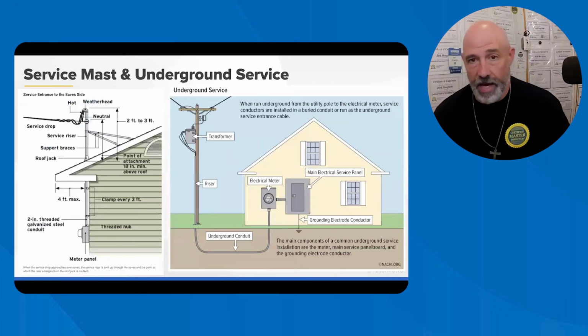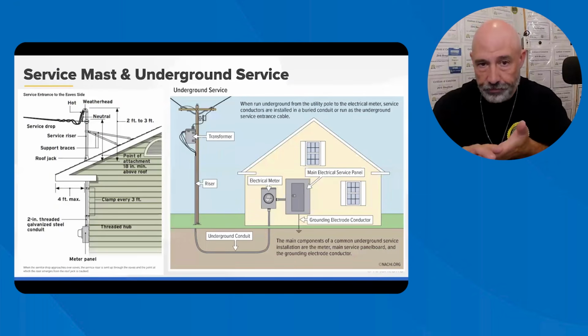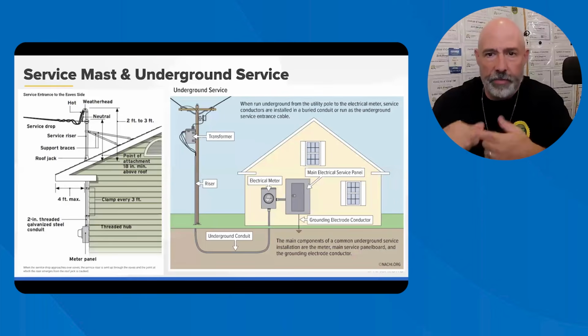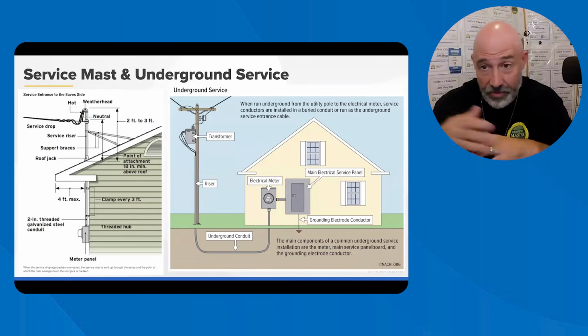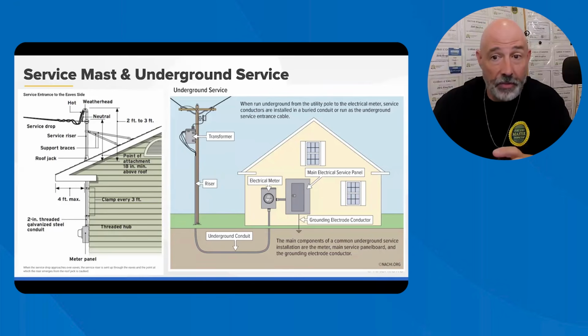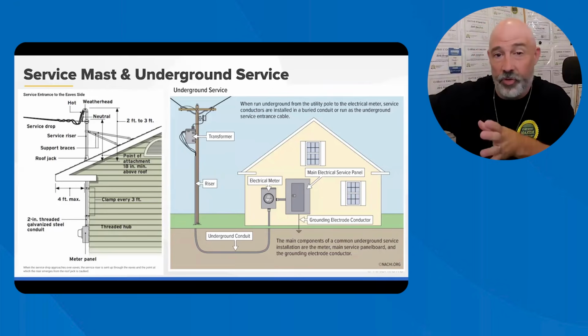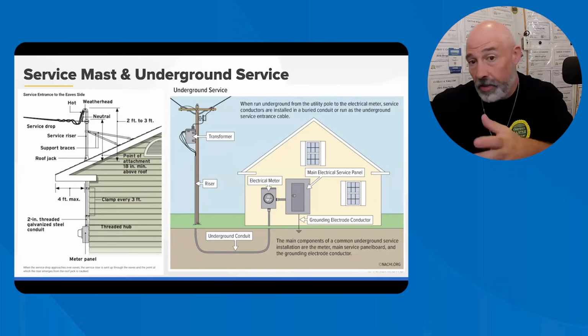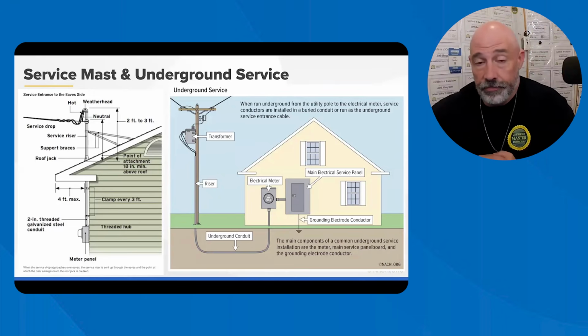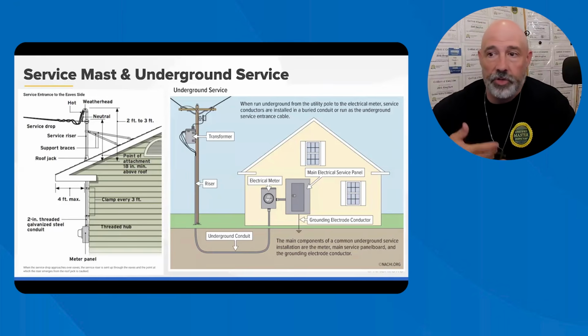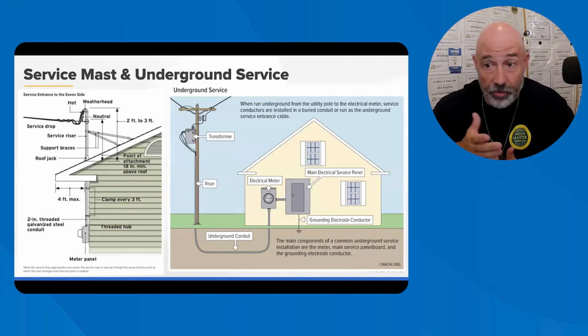So here on the service mast, we're talking about how it's dropped. It typically is located above the eaves. The mast or riser is run through the eaves, or when run underground from the utility pole to the electric meter, a lot of times you'll see that big green box in the yard. It's probably going from that big green box right to the electrical panel. The service conductors are installed in buried conduit or run as underground cable.